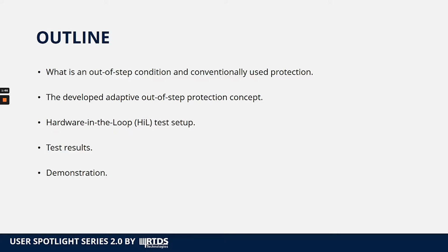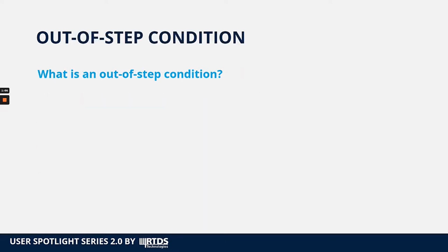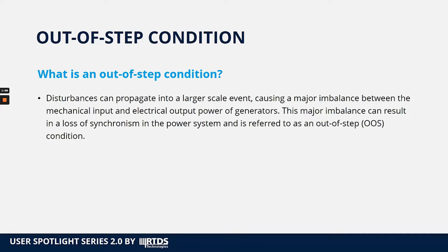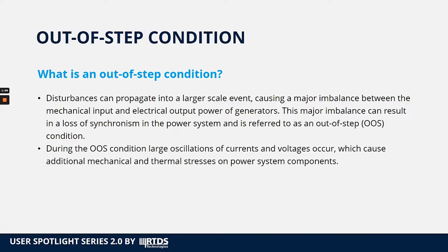So let's get started. First of all, what is an out-of-step condition in a power network? Disturbances in the power network can propagate into a larger scale event, which will cause a major imbalance between the mechanical input and electrical output power of generators. This major imbalance can result in a loss of synchronism in the power system, and this is referred to as an out-of-step condition. During this out-of-step condition, large oscillations of currents and voltages occur, which cause additional mechanical and thermal stresses on the equipment that we have in the power network.